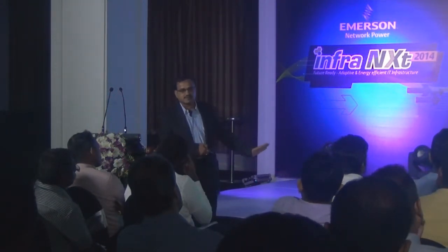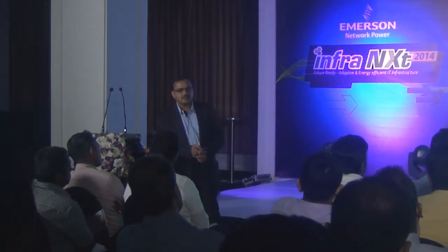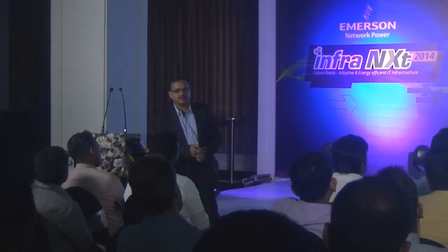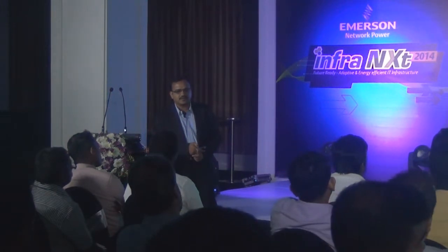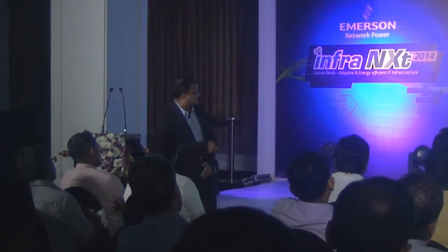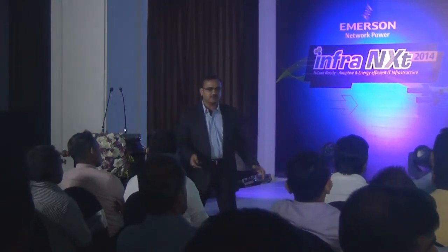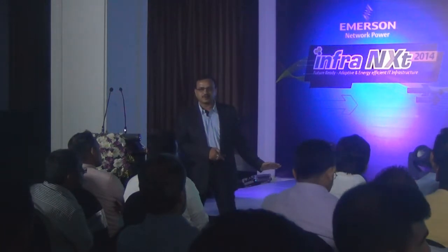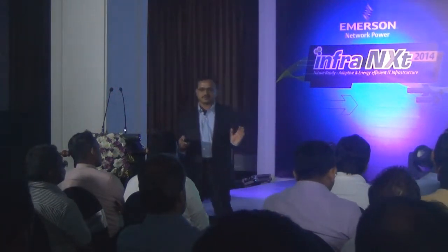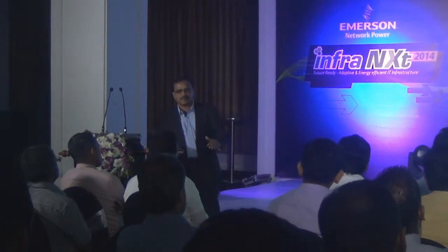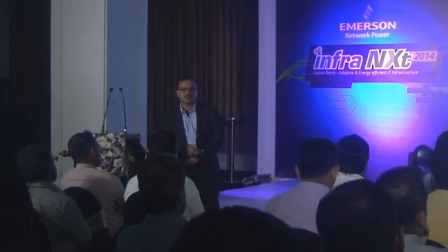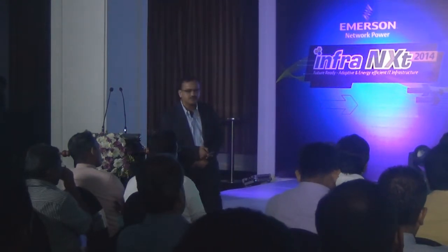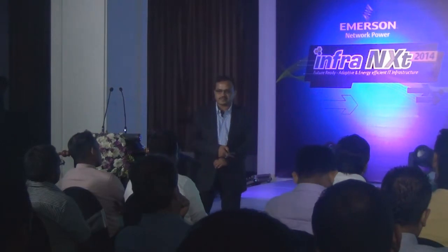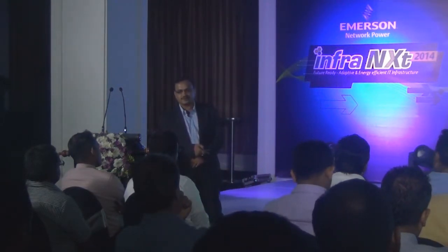We have installed almost around 20,000 sites in India with lithium ion batteries, and the trend has completely changed. This lithium ion battery has its own controller, and that controller talks with the DC power controller to limit the current and voltage to the battery. We call this the CCCV limit, which is essential for battery health, and that is taken care of by the DC power controller through communication between the BMS controller and the DC power controller.